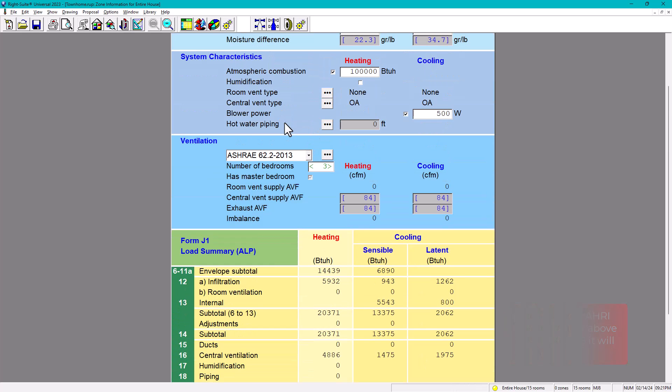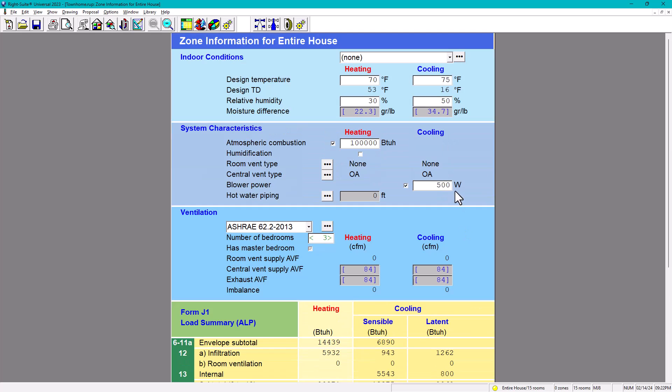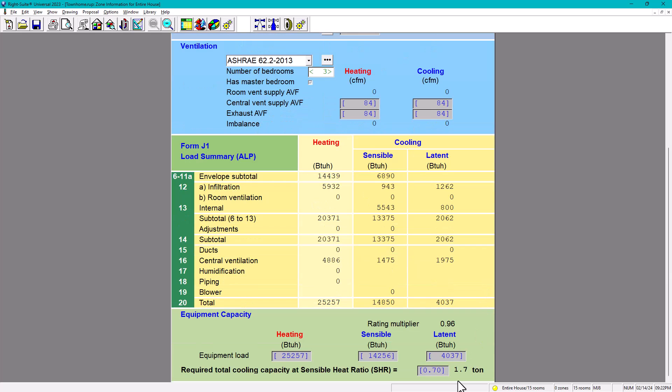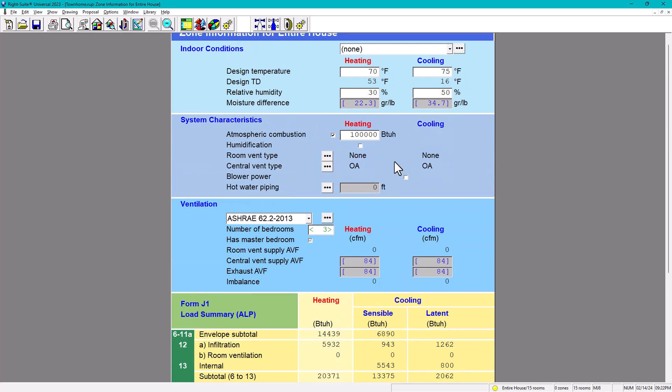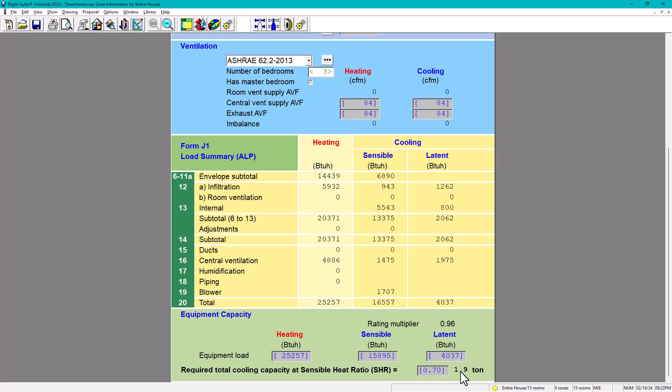So that's why sometimes we just leave it on or we just uncheck it. It's not very relevant I would say, because as you can see, it doesn't change so much. But this blower power is actually very essential because if you have it unchecked, 1.7 ton unit. And I like to be always on the safe side. So if you want to be on the safe side, just click in here, very conservative, 1.9 ton unit, and then you can get a two ton unit. I hope you enjoyed this video and hit the like button. That helps a lot. And subscribe, share and subscribe. I'll see you in the next video.